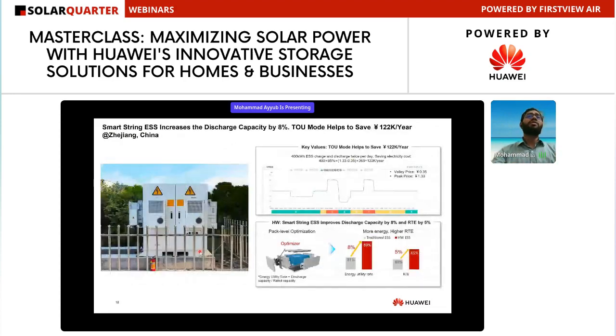If you see another case, this is time of use. This case may not be applicable in the Middle East currently, but it could be applicable in the near future. Let's say when you are taking energy from the grid, and the grid has different electricity tariffs at different times. At peak time there is a high electricity tariff, and at low tariff time you can charge the battery, then discharge the battery during the high tariff time. This will help you reduce your factory's electricity consumption cost, because you may charge the battery during low tariff time and discharge it instead of taking energy during high tariff time, reducing your cost. So this is another case, when you have multiple tariffs during the day.